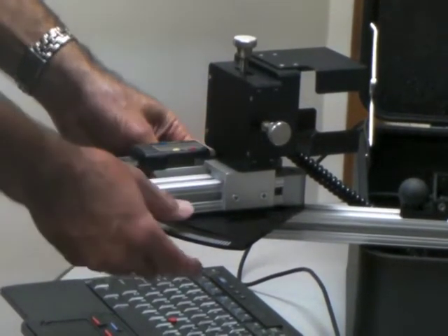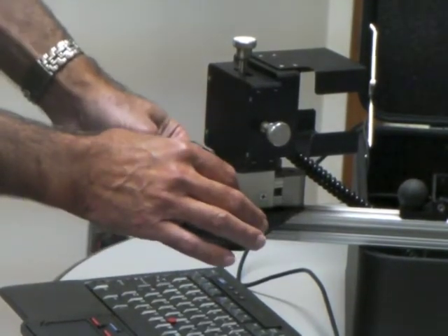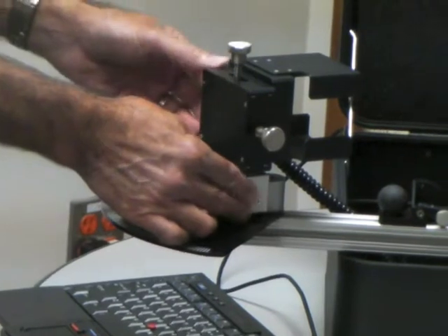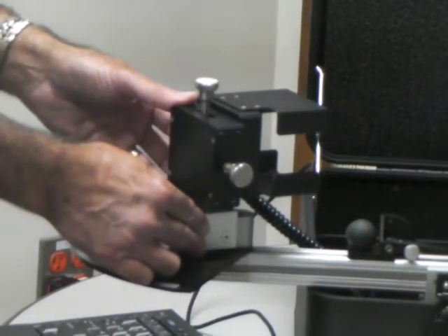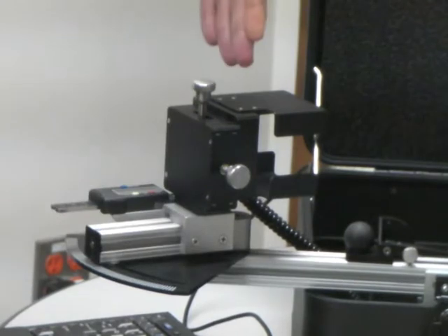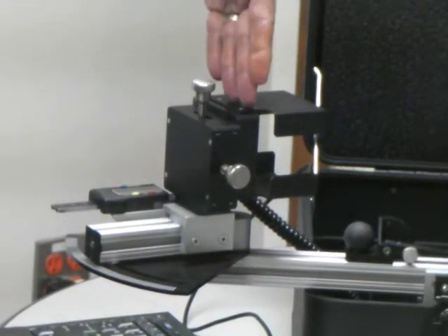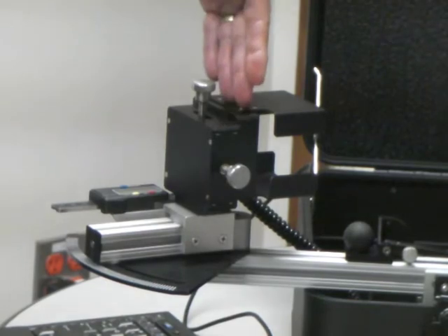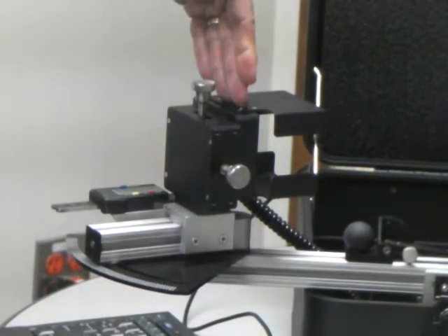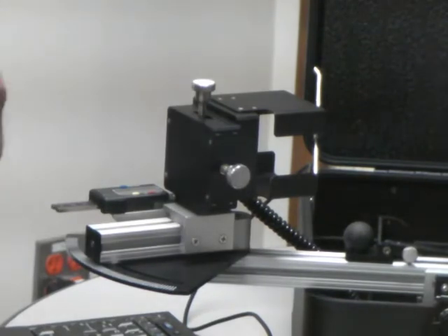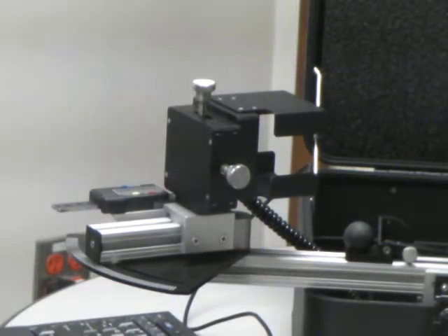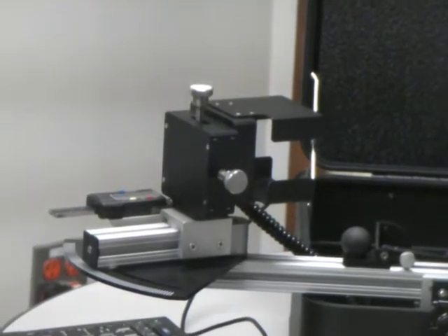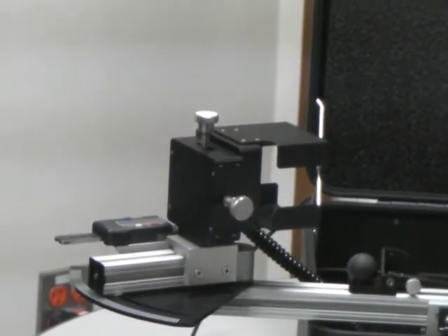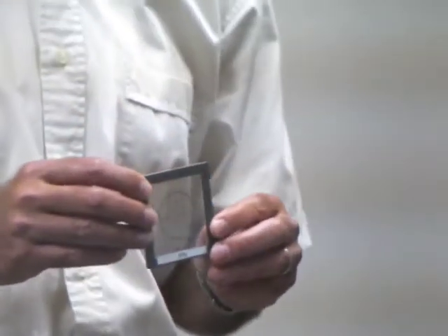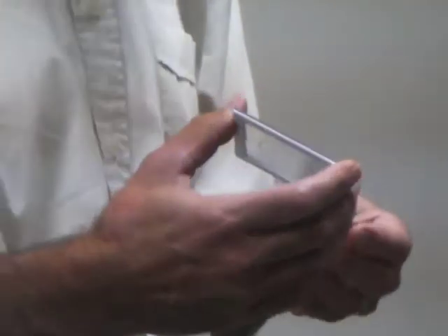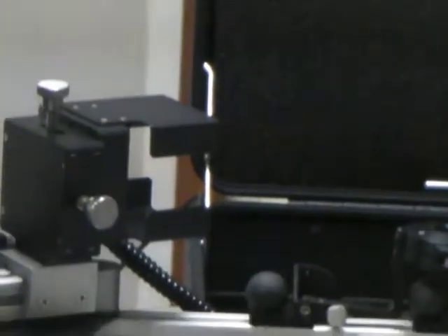The next thing we do is we move the target holder to its full position to the right. So you can see there's a hard stop, and this puts the target plane right at the rotation plane of the target holder. Now we want to put in our setup target holder, which is also the target holder we use for our first measurement, and it's called FOV, for field of view. So this measures the first basic parameters of the endoscope.